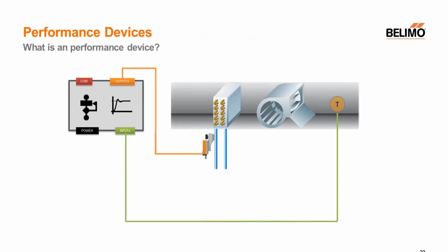So I want to touch on the smart device portion, just briefly, but we use this term, we call things performance devices, and I want to touch on what a performance device is. So again, we'll look at that chilled water modulation example for a fan. Again, this programmable controller is monitoring the discharge temperature, comparing it to a set point, and then modulating the chilled water valve open and close.